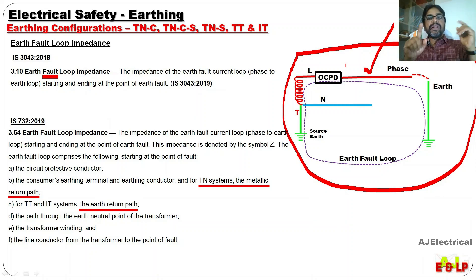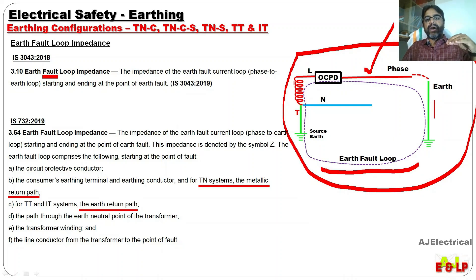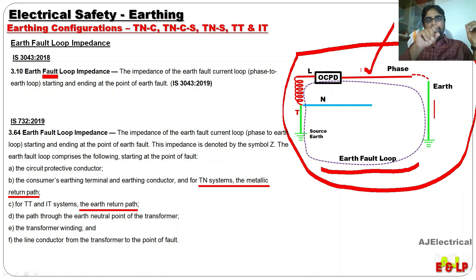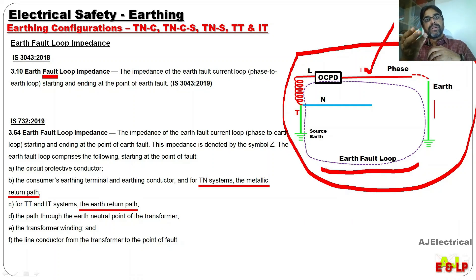That loop will have an impedance. The components of that loop are: the Protective Earth Conductor, the Earth mass — because the current is passing through the Earth — returning to neutral, then the winding, and then the phase conductor or Line Conductor. These components will determine the value of the impedance, and the loop impedance decides the value of the fault current. Depending on the value of the fault current, the OCPD will trip.